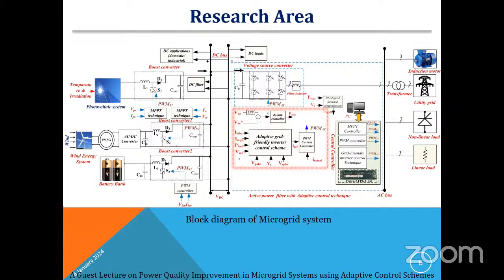So that is the reason we have to develop an adaptive control scheme. So why is the adaptive control scheme required? If you see the DC bus, conventionally the PI control scheme has been used for a long time. But if you see the load variation time, or the grid voltage variation time, what will happen to the DC bus? The DC bus may increase or decrease. But we have to control the DC bus.